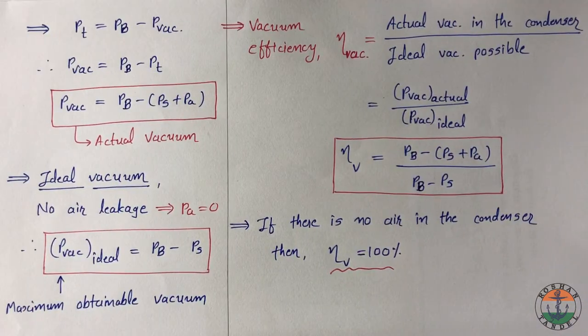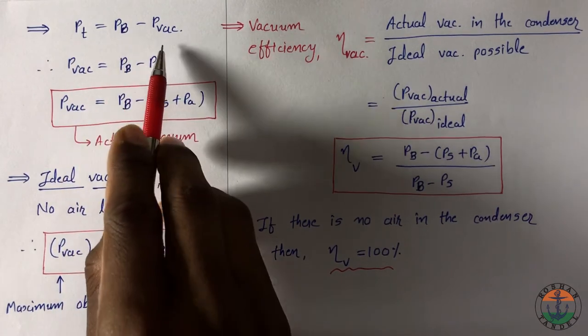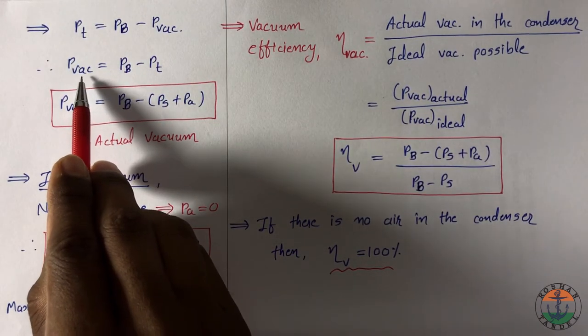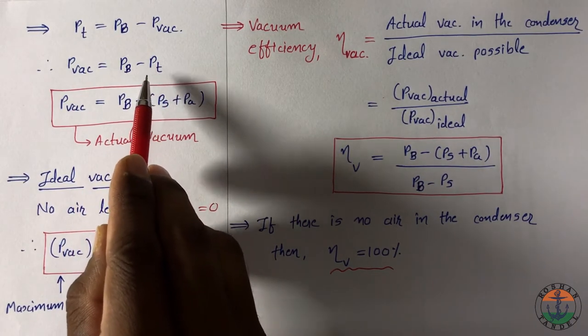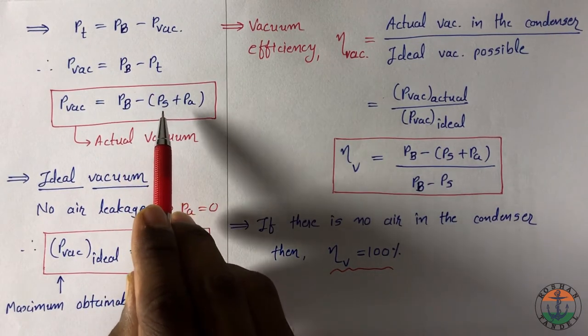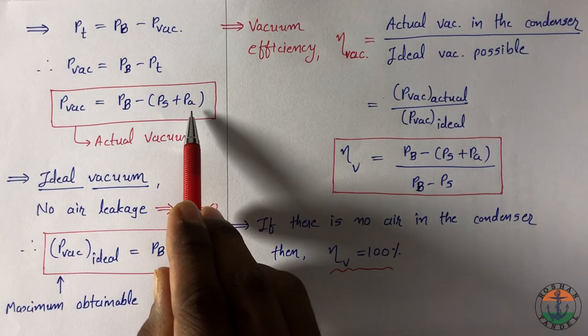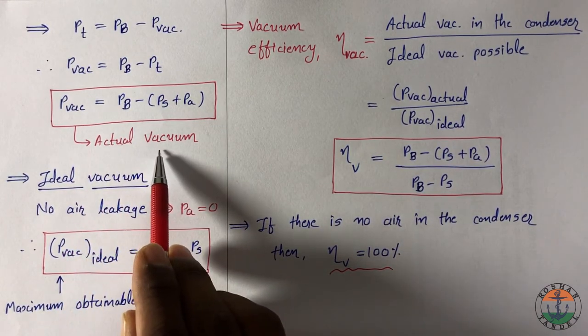From vacuum measurement, we have the equation total pressure is equal to barometric pressure minus vacuum pressure. So vacuum pressure will be Pb minus Pt, here Pt is the total pressure in the condenser which is the sum of partial pressure of steam plus partial pressure of air. So this is the actual vacuum present in the condenser.